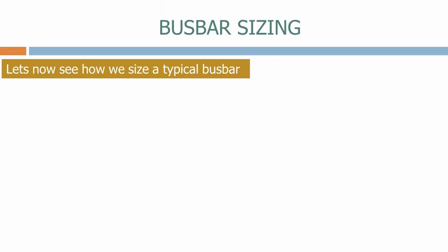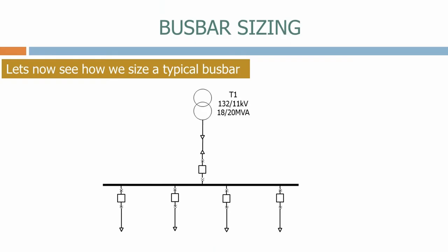Let's now see how we size a typical busbar. Here we have a 132 to 11 kV transformer, rated at 20 MVA, feeding a busbar through an incomer. The maximum current that will be fed into the busbar will depend on the power rating of the transformer. The power of the transformer equals root 3 times its maximum voltage and current ratings. Therefore, the maximum current equals the power rating divided by root 3 times its voltage rating.